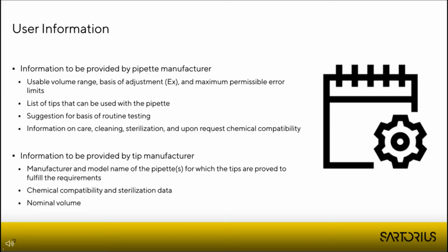And then user information, a small collection of different factors that the manufacturer must provide. Usable volume range. This is something you need to always have marked on the pipette. So minimum and maximum volume in the case of an adjustable pipette, or if it's a fixed volume pipette, then obviously it's just a fixed value. Basis of adjustment, so at which temperature the pipette was adjusted. And then maximum permissible error limits. Those can differ from the ISO standard. They can't be worse, but they can be better. List of tips that can be used with the pipette.